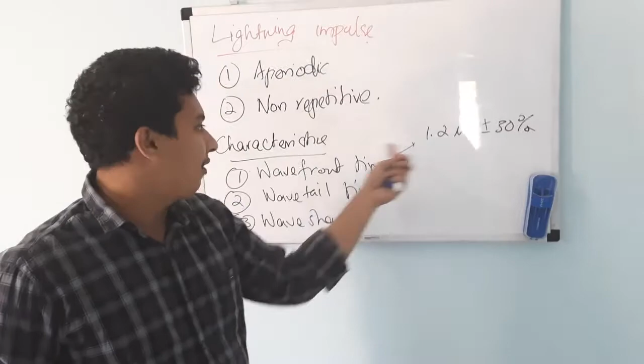Wavefront time usually comes to about 1.2 microseconds, but since it is non-repetitive, we have a threshold value of plus or minus 30% for wave front time. Then for wave tail time, you have around 50 microseconds, and that also has a threshold value of 20%. This means you can have a variation within this range, because it is quite a natural phenomenon and not repetitive.